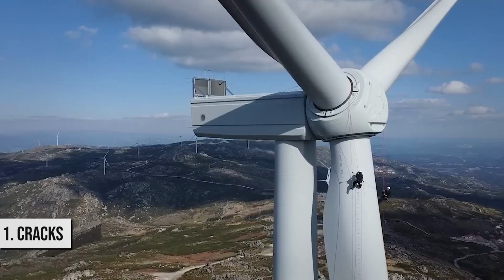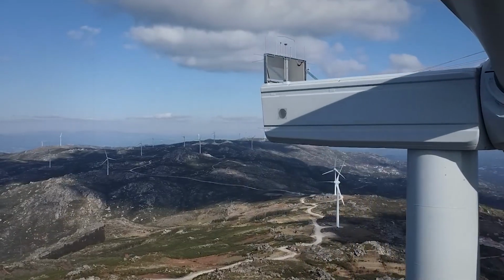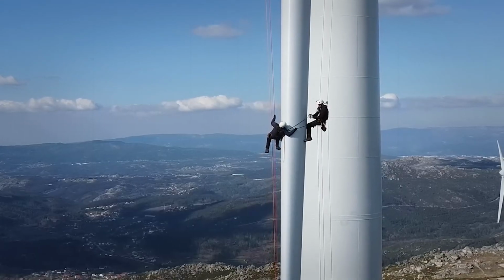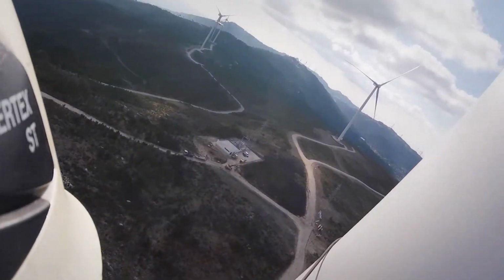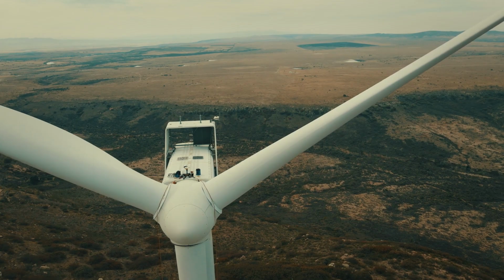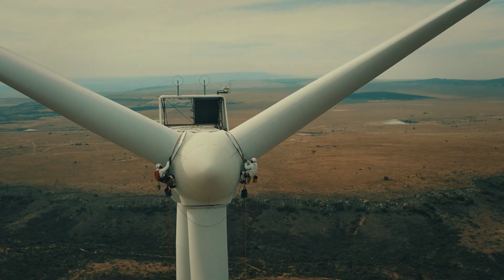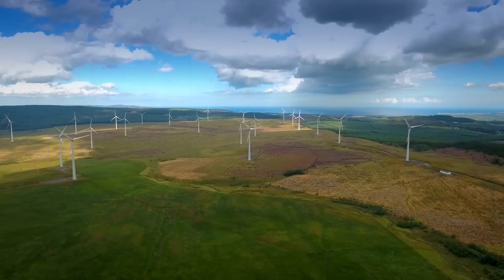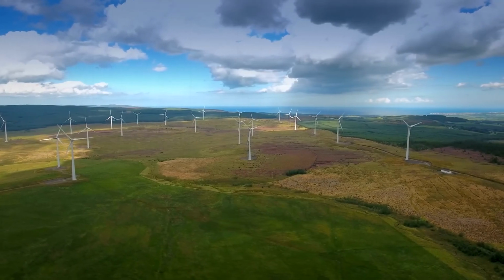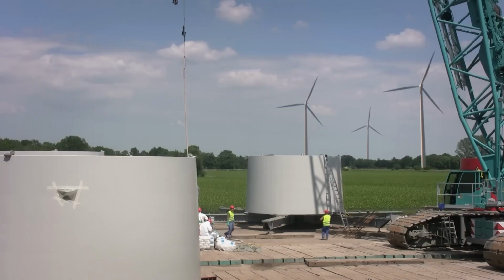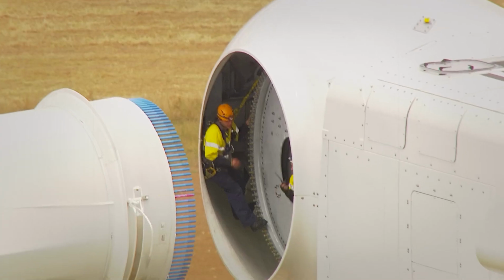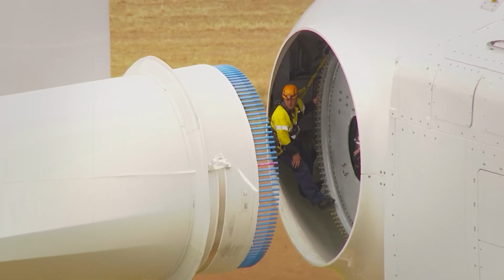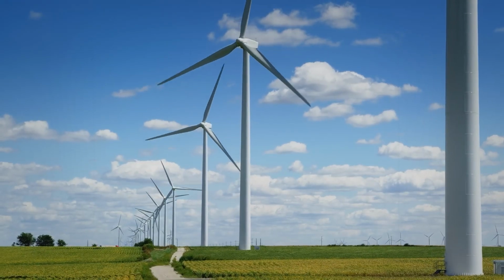1. Cracks. When it comes to flaws, cracks are among the most common and potentially hazardous mistakes that technicians face. They may provide the appearance of minute surface lines, or they may develop into significant structural breaches. Fatigue stress is caused by the continual rotation of blades. Environmental stress, which may be caused by high wind gusts or storms. These are the most prevalent causes of fractures. Impact damage, which may be caused by things like debris or bird attacks.